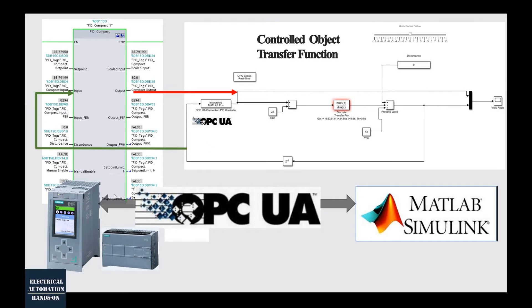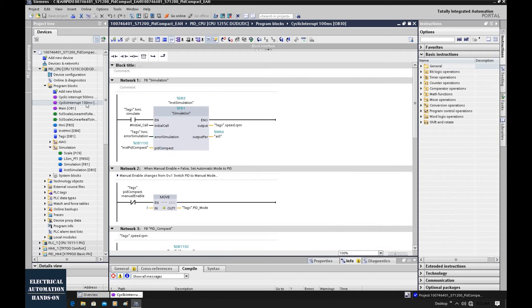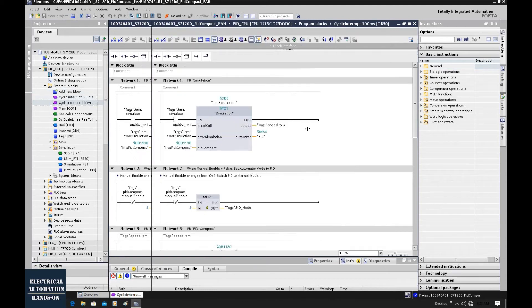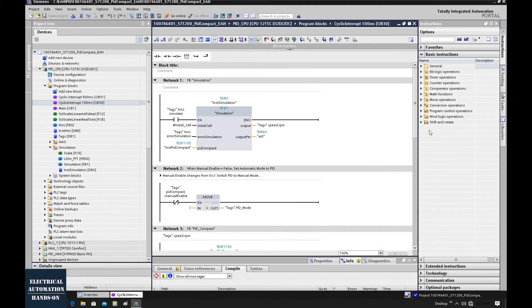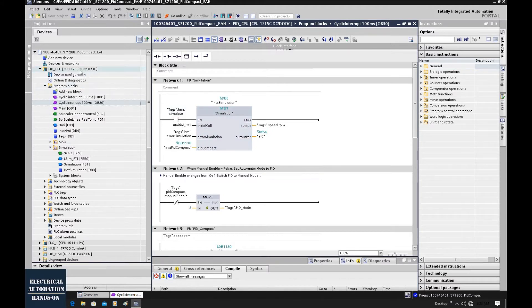Alright, let's go to the TIA portal. This is the Siemens PLC programming software named TIA portal. The latest version is version 16. Highly recommend you use the latest version, because to enable the OPC UA server function, we usually need the latest firmware from the controller. For example, for this S7-1200 PLC, it needs firmware version 4.4, and TIA portal version 16 supports that.